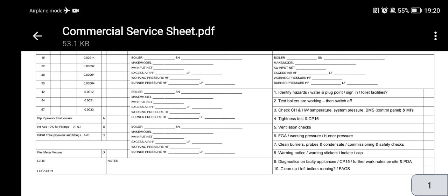Step ten: clean up. Make sure you don't forget any tools — walk around the plant room, check you've got everything, and make sure it's better than how you found it. Note anything the plant room should have but doesn't. Make sure the boilers are left running — check temperatures. Then do one last check: go around and check your flues, air, gas, and safety devices, because you may have interrupted the gas supply or removed a flue test point. Double-check everything is in place — it doesn't hurt.